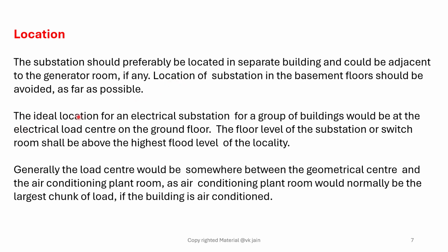The ideal location for an electrical substation for a group of buildings would be at the electrical load center on the ground floor. The floor level of the substation, of which the switch room shall be above the highest flood level. Generally, the load center would be somewhere between the geometrical center and the air conditioning plant room, as the air conditioning plant room would normally be the largest chunk of load if the building is fully air conditioned.